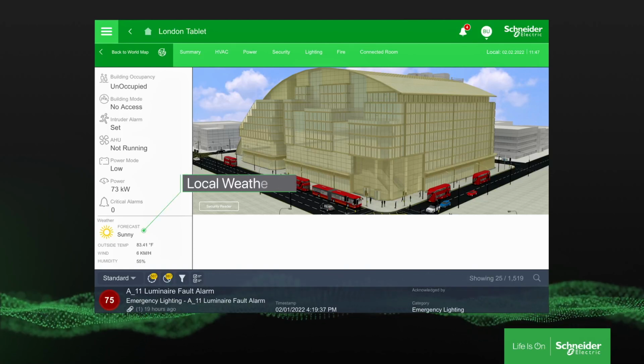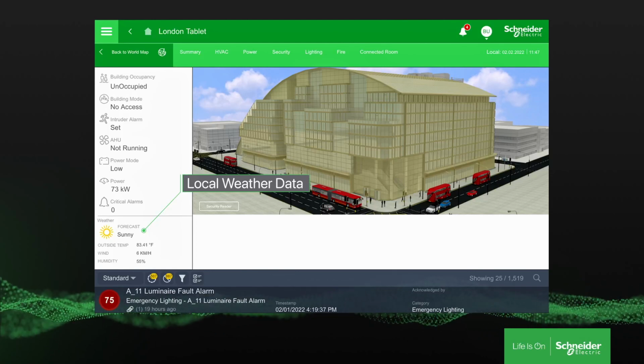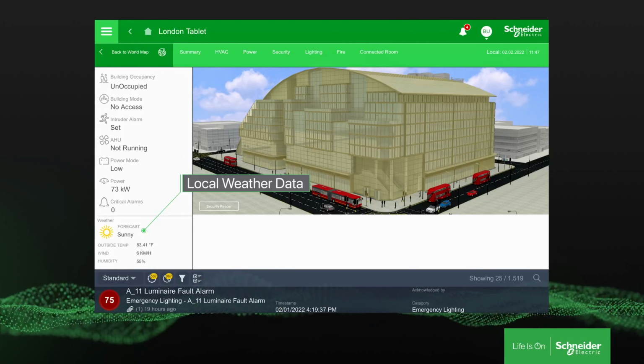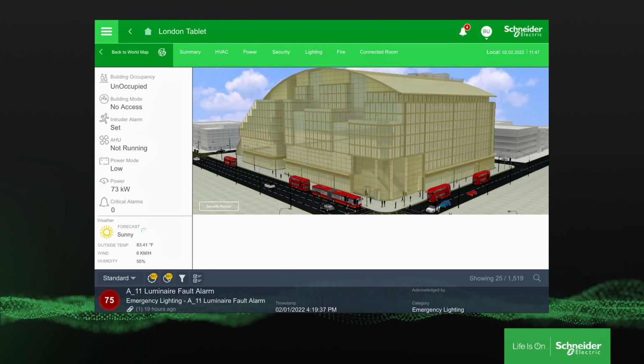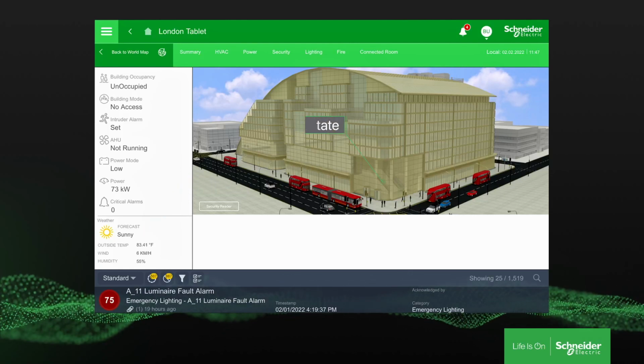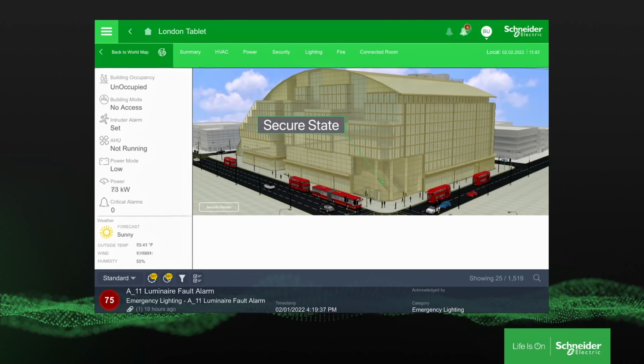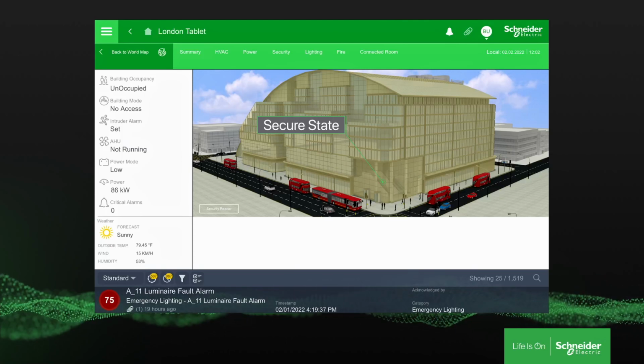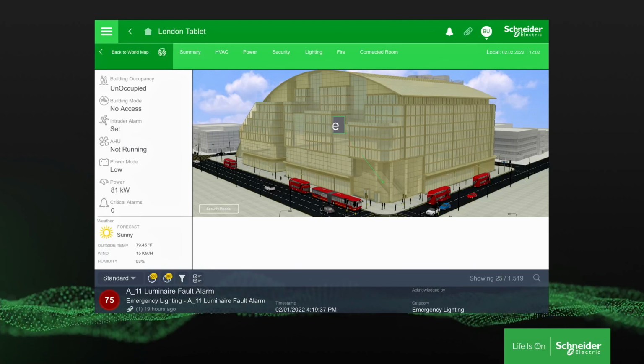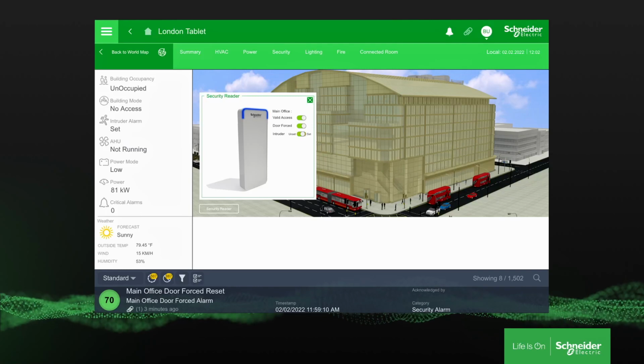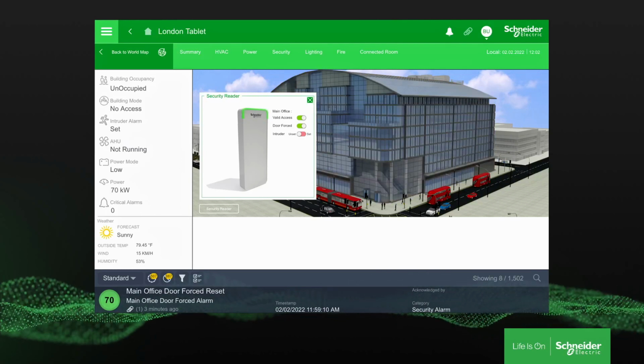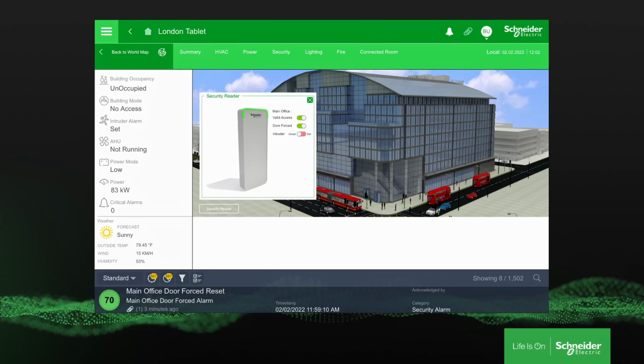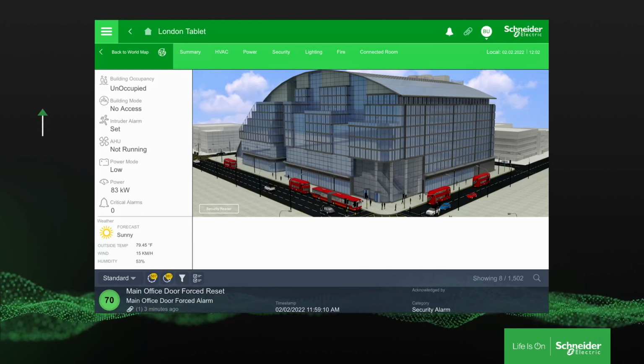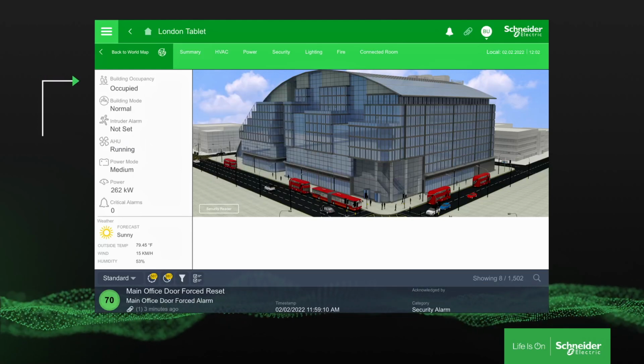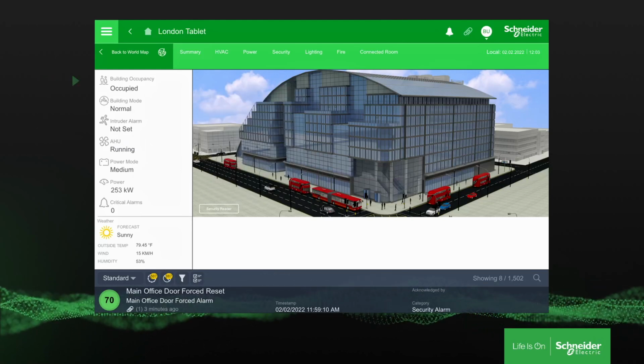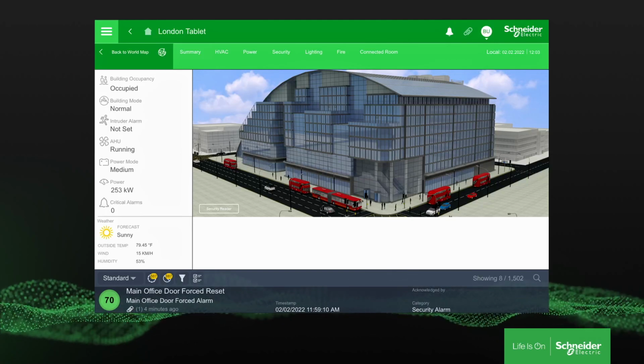We can see the local weather data that is brought in via web service connection to a global weather service. Before swiping, I can tell you the building is in its secure state by the gold colored overlay on the building graphic and the fact that the systems are in the overnight unoccupied mode. After swiping, the intruder alarm is disabled, the entire system is waking up into the programmed occupied mode. The HVAC, power and lighting automatically adjust as we start the business day.